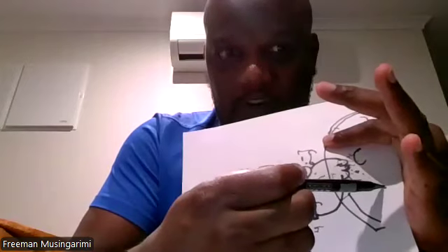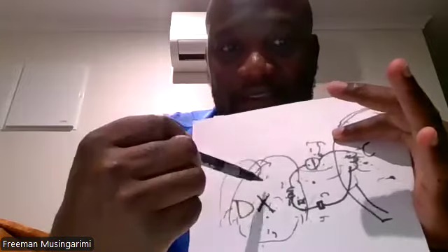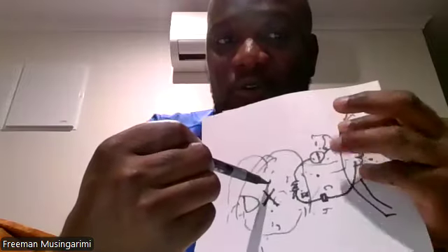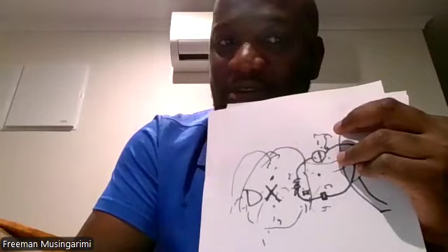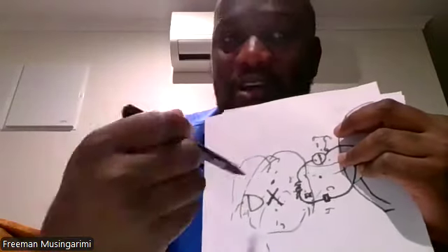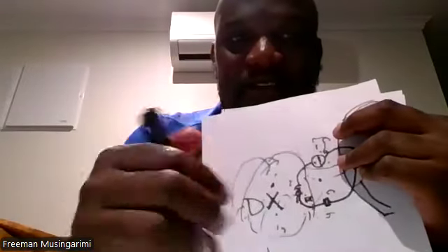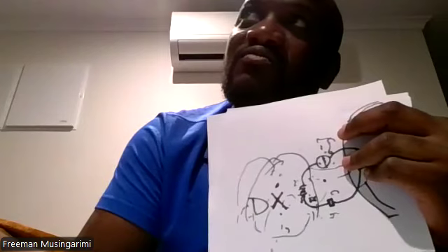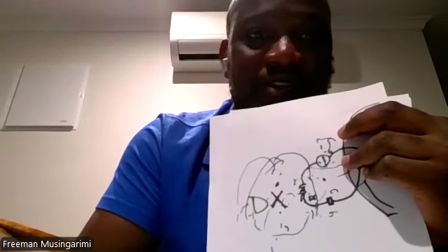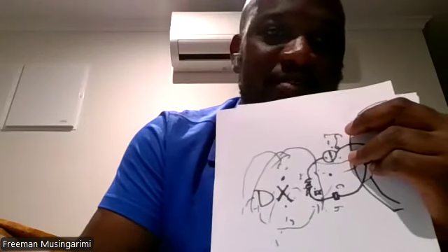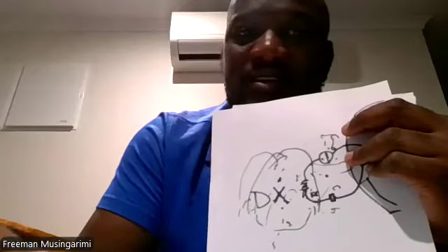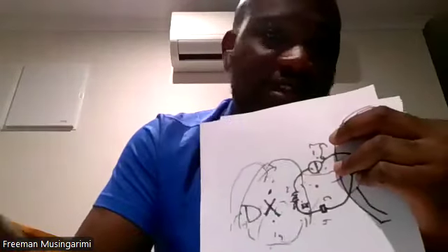So you just remember 3 circuits: the condenser water here, the DX, and the evaporator that takes chilled water into the building, into whatever we are trying to cool. A data center for us, for example. It just takes the water back, so it can go in the building. I think around 9 to 13 degrees. When it comes out of the building, it's probably around 18 degrees. So that's the heat. That's all they want to take out. So it comes back. Then this will take it again.